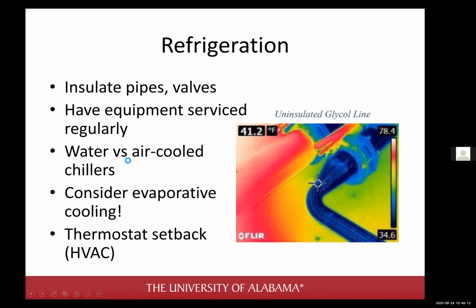Water versus air-cooled chillers. This is a topic I'm not going to talk too much about, but if you can have a water chiller that's attached to a cooling tower, it's going to be like double the efficiency of a water chiller where the condenser is cooled via air. If you can, here's another best practice. If you can use 85-degree Fahrenheit water to do your cooling in your process, please consider evaporative cooling. What I'm talking about is a cooling tower.